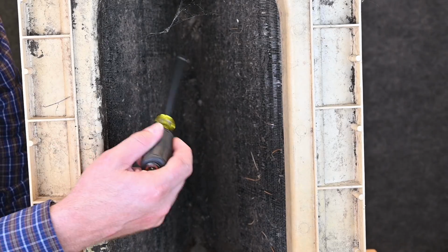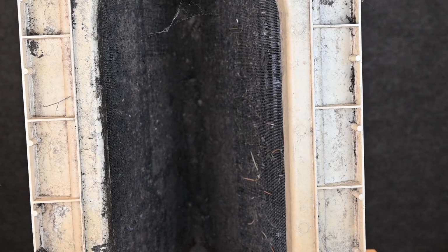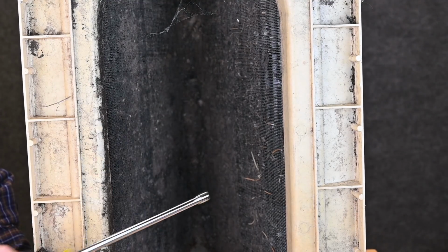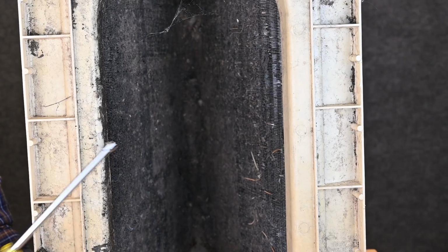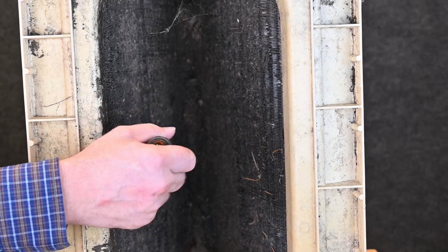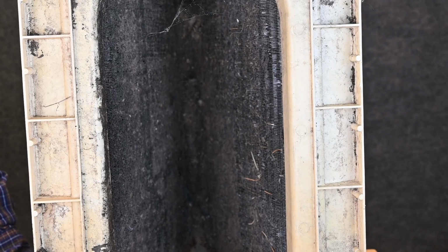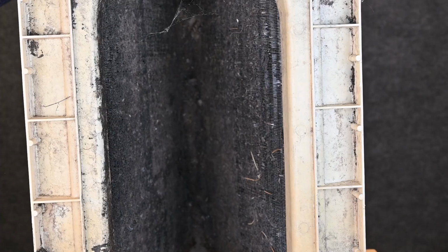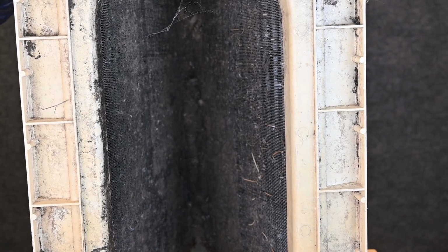So if we see this kind of evaporator coil, it's not only blocking airflow, it's also stopping heat transfer. Superheat and subcooling on this system really isn't going to matter because we have an airflow issue. Even the people that will look at only pressures, this is going to be a huge issue. So seeing the airflow, checking this evaporator coil is very, very, very important.